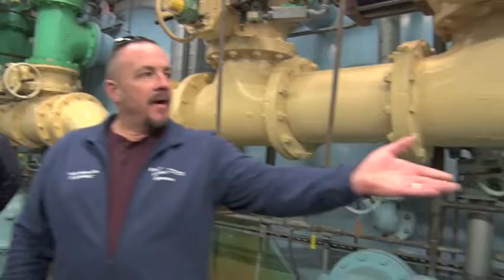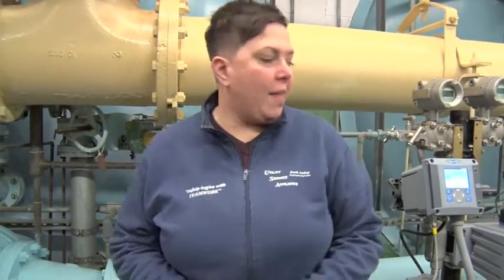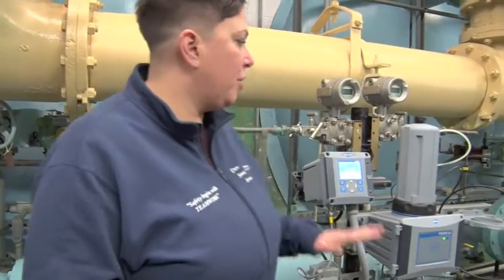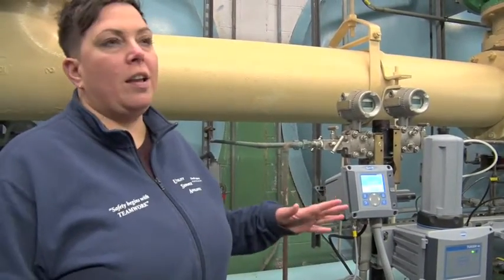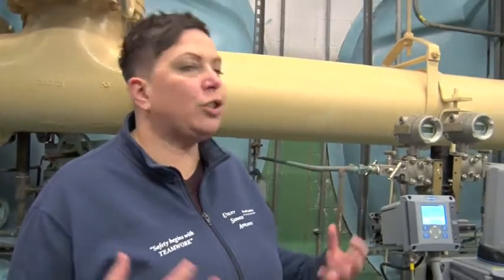I don't know if you want to talk a little bit about the turbidity meters. Yeah, so we have to monitor for turbidity, and that's what these analyzers are. These are constantly running, and like Richie was saying, every 15 minutes it takes a reading. So we're able to see the turbidity, meaning how turbid the water is, how cloudy it is. Regulations by the state are that we have to produce a certain amount of turbidity leaving the plant, or else that's a violation. So we constantly have to monitor it, and that's how we do it, with the online analyzers.